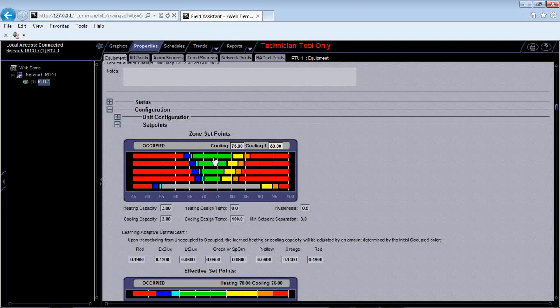The three bars on top of here are actually set up for demand limiting or load shedding. What that is, if you are reading on your building automation system, for instance, the power metering or the peak loads that are coming into your building, you can actually read those values and broaden your set points based on when your loads are peaking. So in order to save money whenever you're spending most on energy, you want to broaden your set points so that you don't use the equipment as much and you don't use as much electricity.